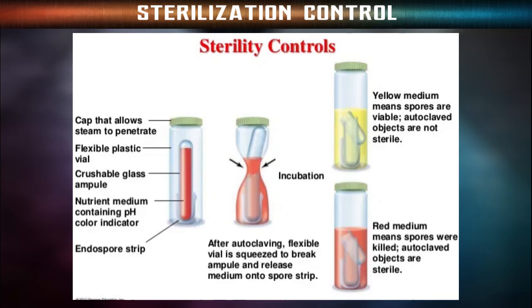Several methods are available to ensure that autoclaving achieves sterility. The effectiveness of the sterilization done by an autoclave can be monitored by a biological indicator, which is spores of Geobacillus stearothermophilus, formerly called Bacillus stearothermophilus, the best indicator because they are resistant to steam. These spores are killed in 12 minutes at 121 degrees Celsius. The Center for Disease Control recommends weekly autoclaving of a culture containing heat-resistant endospores of Bacillus stearothermophilus to check autoclave performance. The spore strip and an ampoule of medium enclosed in a soft plastic vial are available commercially.